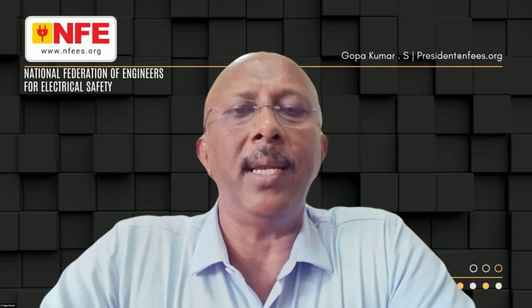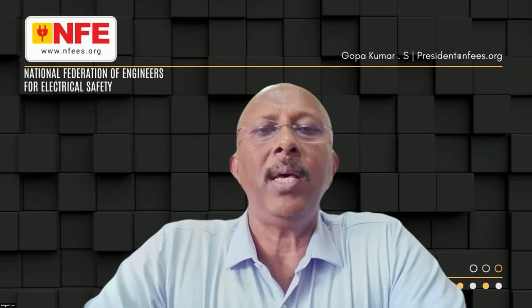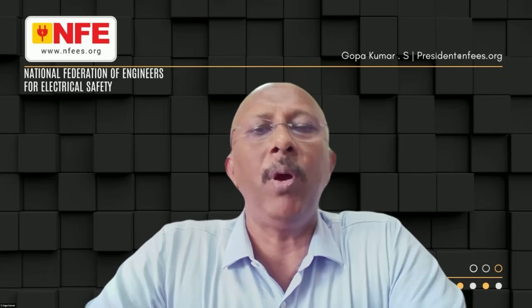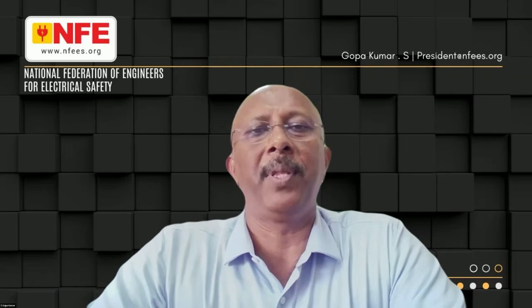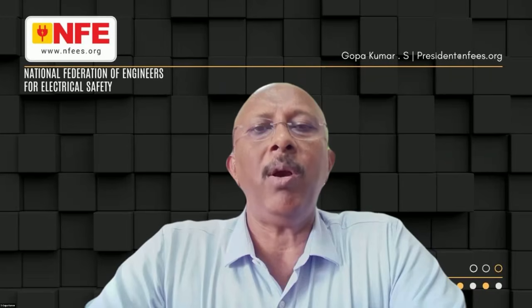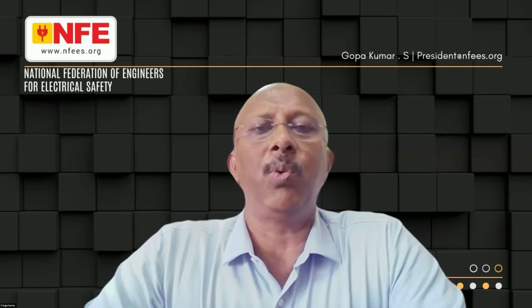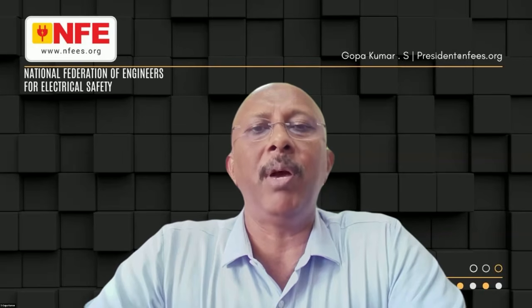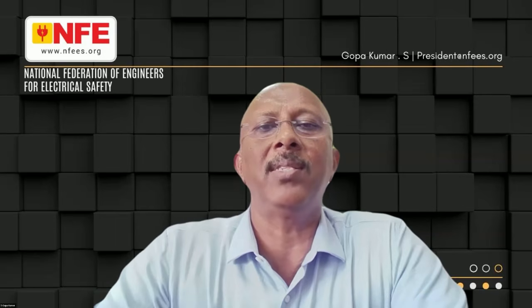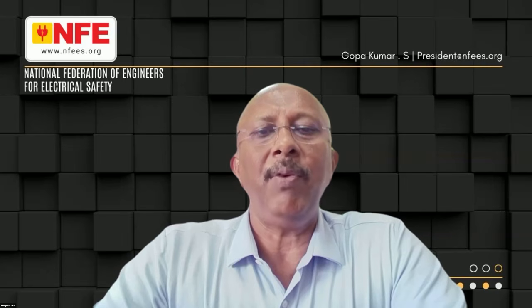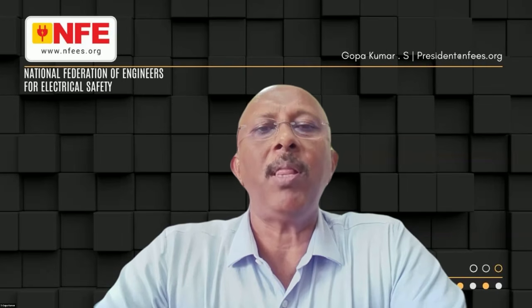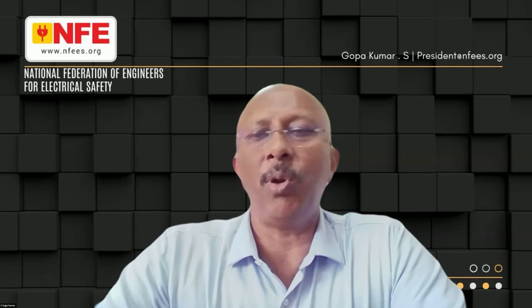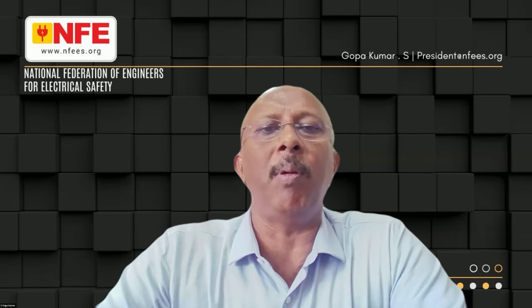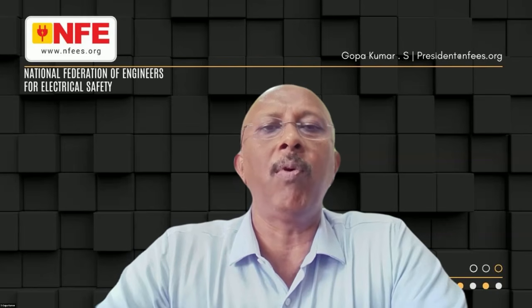In a good electrical installation, the wires are selected based on the protective device. That means you can use it for a certain load safely. And if you are overloading, the protective device is supposed to trip. So you cannot overload a circuit if it is in good condition, because the protective device will trip. Once your protective device trips, you are in a safe situation. But if your protective devices are not rated properly for overload, then you are in trouble. So overloading is not the problem. Protective device not operating during overload is the problem.